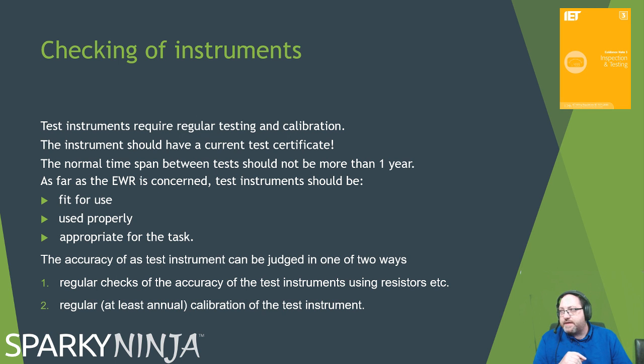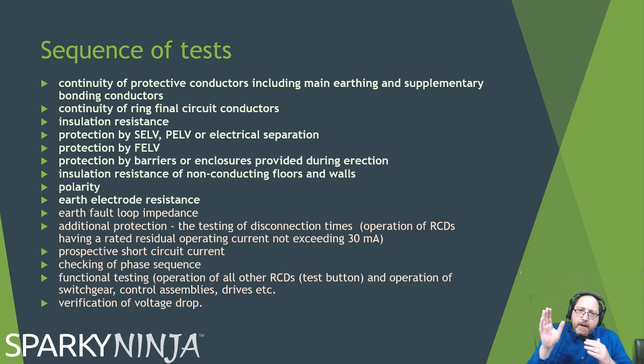The tests. There are lots of them. This is the full sequence of tests. Continuity of protective conductors, including main earthing and supplementary bonding. Continuity of ring final circuits. Insulation resistance. Protection by SELV, PELV or electrical separation. Protection by FELV. Protection by barriers or enclosures provided during erection. Insulation resistance of non-conducting floors and walls. Polarity and earth electrode resistance.